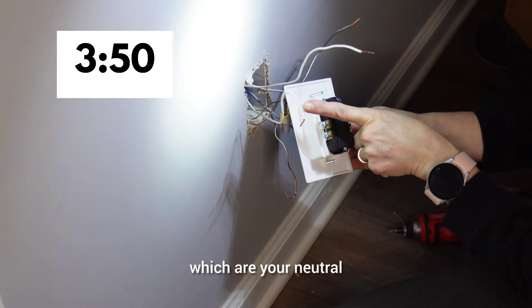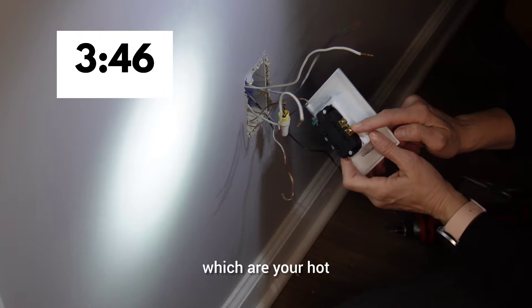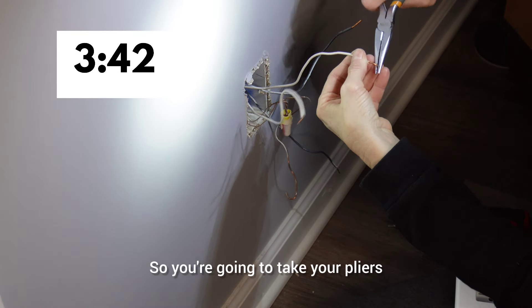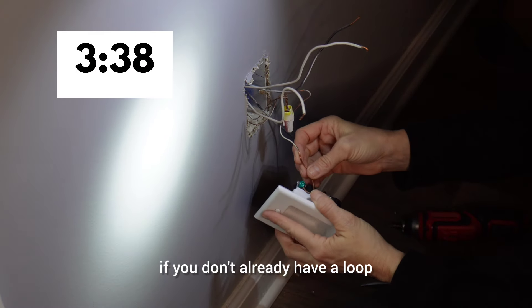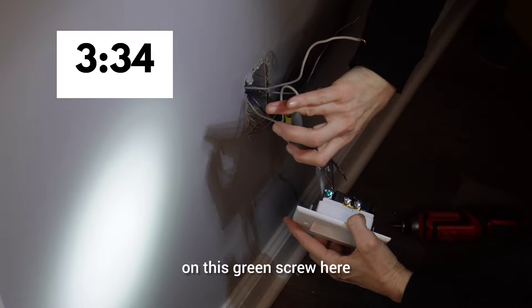The white wires, which are your neutral, are going to go on the silver screws here. And the black wires, which are your hot, will connect to the brass screws. So you're going to take your pliers. We're going to make a little loop in the wire if you don't already have a loop. And first, we're going to put the ground wire, which is the copper wire, on this green screw here.